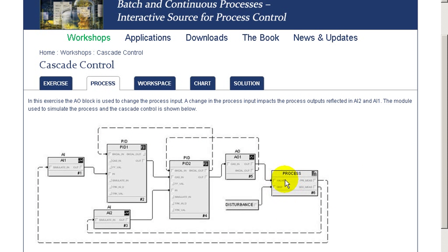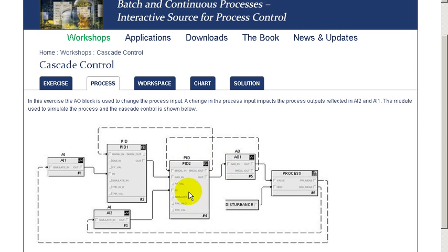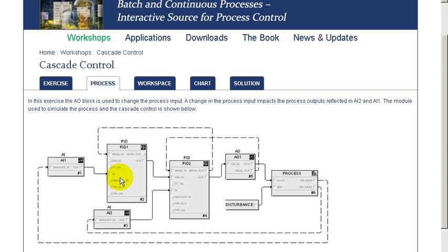In the exercise, we have a dynamic process simulation in which the disturbance is used as well as the manipulator parameter to determine two process outputs. One process output responds very quickly to any input change — that output is used in the slave loop as its control parameter. The second output responds much slower and is the input to our master loop. Through this combination of master-slave, we're able to very precisely maintain our setpoint of our master loop.